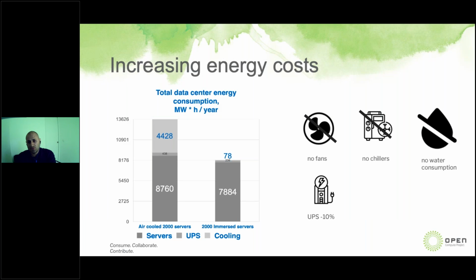Immersion is an extremely energy efficient technology. The general answer is that immersion solutions are overall more efficient, with PUE extremely close to 1 relative to an air-cooled data center with PUE closer to 2. On the graph, you can see that total energy consumption in immersion is lower than just the IT load in the conventional case. At the server level, the absence of air cooling fans reduces energy consumption, and generally servers use less energy in the cooler environment.